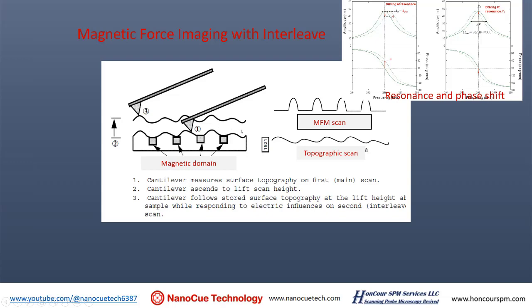The tip scans over the sample the first time with feedback to collect topography. On the second scan, the tip lifts at a separation distance and scans over the sample, recording the phase shift. This phase shift represents the magnetic field — of course, the tip and sample must have a magnetic force between them. So the tip must have a coating of magnetic material, typically cobalt or some other magnetic material, making the tip itself a magnet. The magnetic field between sample and tip produces attractive or repulsive force, causing the phase to shift, and you record that phase as the magnetic field reading of your sample.